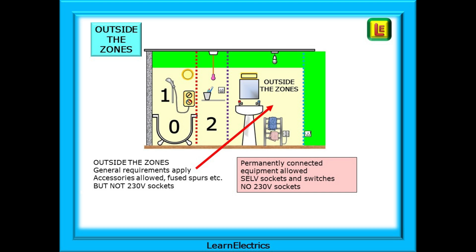Moving to the space called outside the zones — this used to be known as zone 3 many years ago, but not anymore; another exam catch-you-out, as lots of people still think of it as zone 3 when, according to the regs, it isn't. In this outside zones space, most of the general requirements of the regulations apply. Accessories such as fused spurs, switched FCUs, etc. are permitted, but not 230 volt sockets.